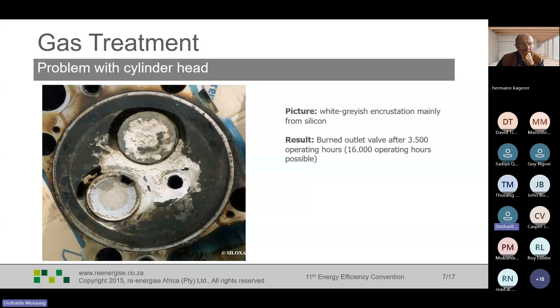To summarize the problems from each impurity: moisture, because we have hydrogen sulfide, can lead to sulfuric acid forming if it condenses, so we need to remove moisture. We get deposits in the gas control system from moisture, leading to malfunctions in equipment and pipe blockages. It can reduce efficiency in the entire system, where water puddles form, gas transmission suffers, and your CHP might get stuffed or have vibrations because of oscillations in gas flow.